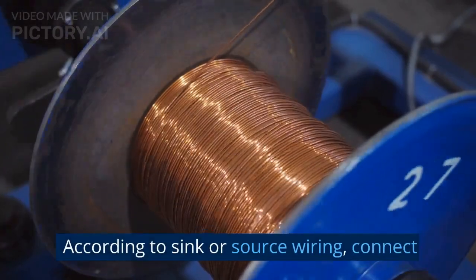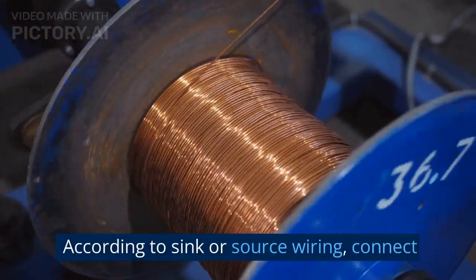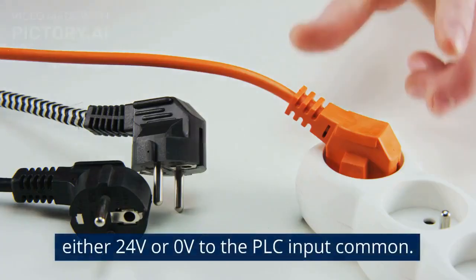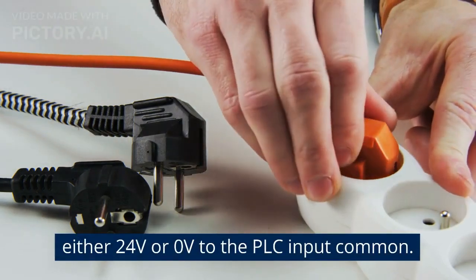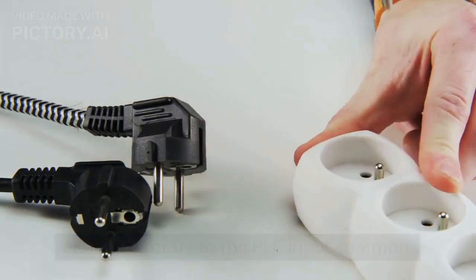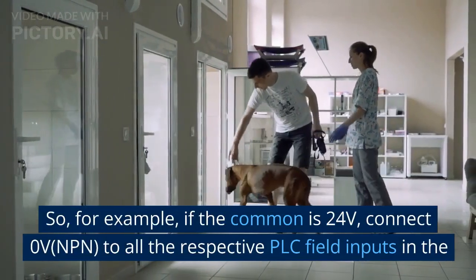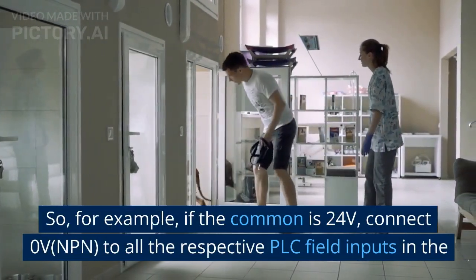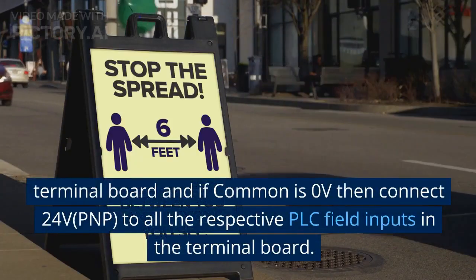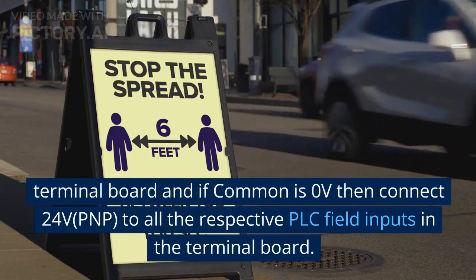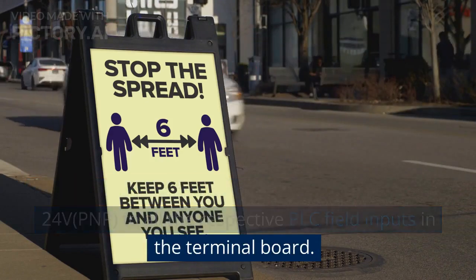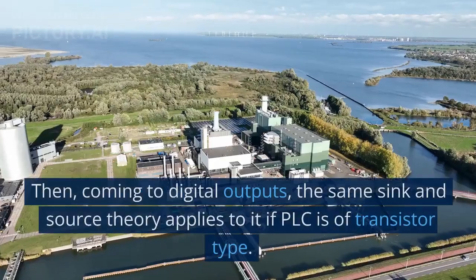According to sink or source wiring, connect either 24 volts or 0 volts to the PLC input common. So, for example, if the common is 24 volts, connect 0 volts NPN to all the respective PLC field inputs in the terminal board, and if the common is 0 volts, then connect 24 volts PNP to all the respective PLC field inputs in the terminal board.